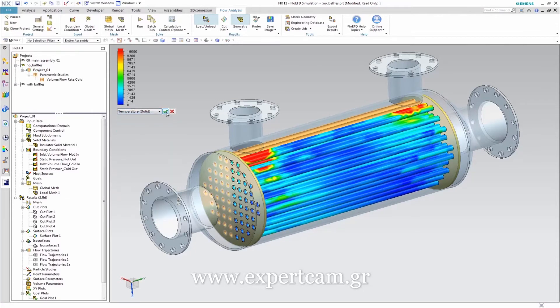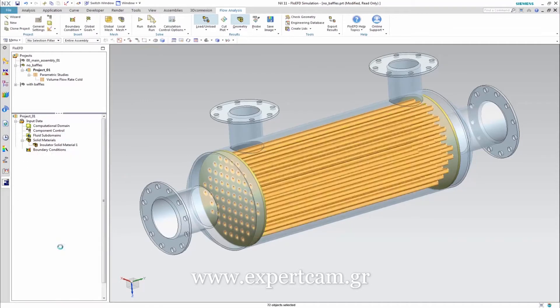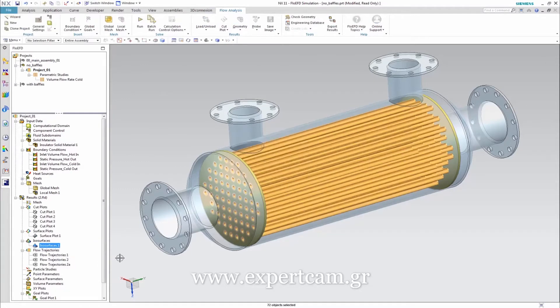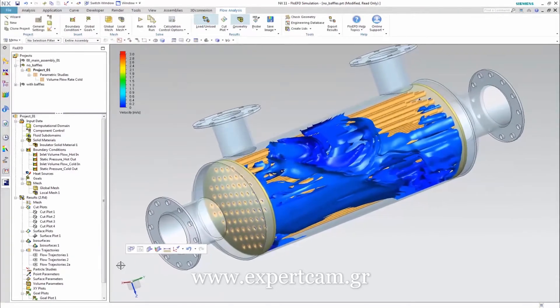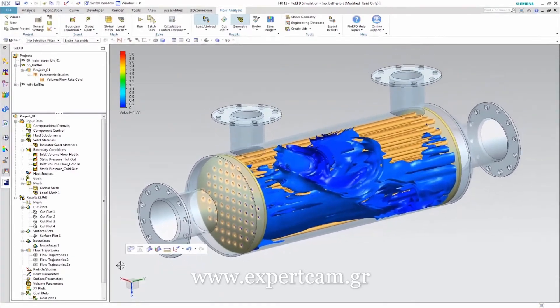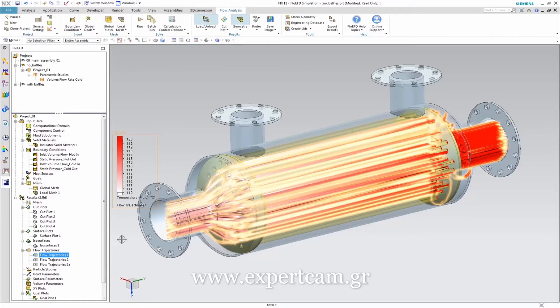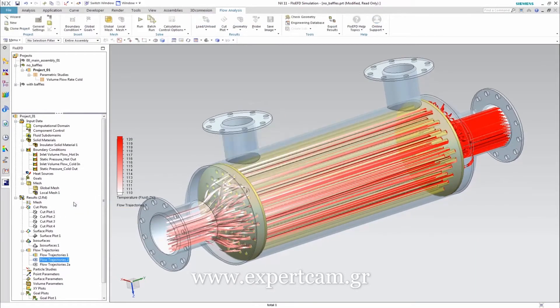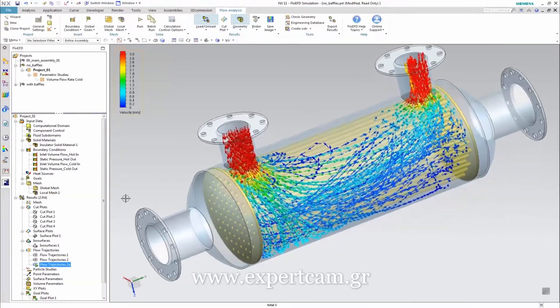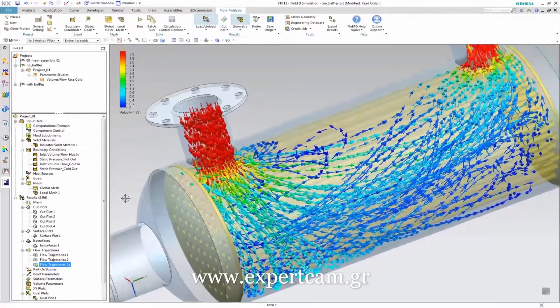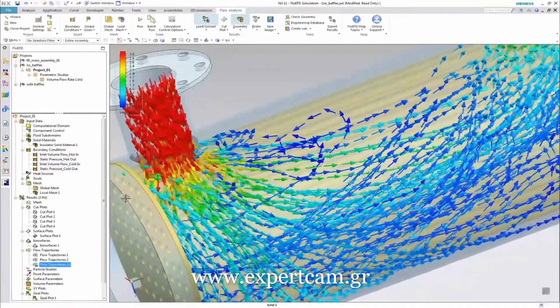Here we can see the solid temperature on the tube surfaces. The ISO surfaces show regions for a specific value of the defined display parameter. In this case, we see regions with a very low velocity, which is usually not desirable for such applications. We use the flow trajectories to illustrate the flow in the hot side and in the cold side. Considering the arrows, we can also observe regions at low velocities, and in addition, we see a nearly parallel flow to the tubes.